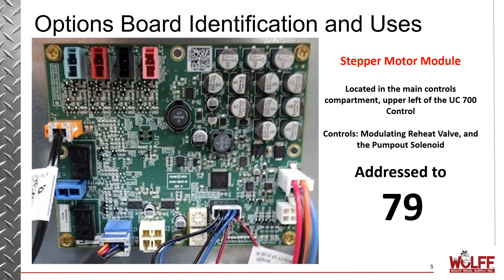The stepper motor module is located in the main controls compartment, which is positioned in the upper left of the UC 700 control board. This controls the modulating reheat valve and the pump out solenoid. This board needs to be addressed to 79.